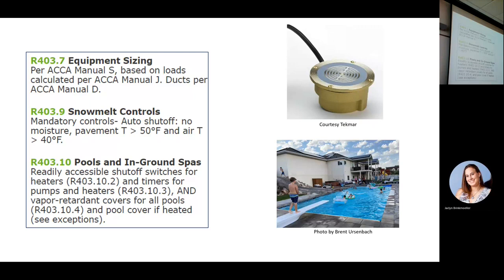So if you have enough money to put in a snow melt system, you need to spend a little bit of that and put in a control that's going to cost you another $1,000. And what it does, it senses slab temperature, it senses air temperature, and it senses moisture. And it cuts the system off when it's not needed, and it turns it on when it's needed. I put in a number of these things, and they work really slick.